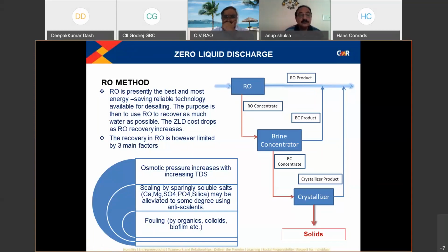And if we are treating the cooling tower water in our system, then there is a stiff challenge from phosphate as well as silica, as a single antiscalant is not available to take care of both chemicals. So these contents are controlled by the lime dolomite process in a clarifier only. We subsequently reduce around 45% of that content in the effluent. The inorganics are taken care of by proper chemical dosing, as in the schematic drawing shown.